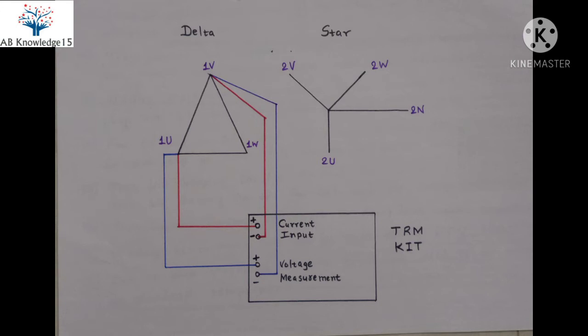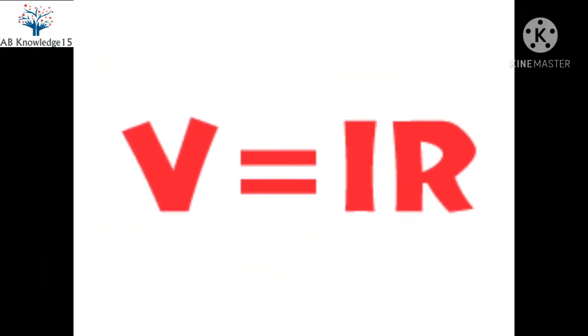For the star connection of winding, as in the case where the secondary winding is star connection, we have to connect the TRM kit phase to neutral, like 2U to 2N, 2V to 2N and 2W to 2N terminals of the transformer. After any of these connections of the test kit to the transformer, switch on the test kit, apply a suitable current range and note down the winding resistance values when we get stabilized values. In all of these measurements, the current injected by the TRM kit develops a voltage drop and resistance is measured as per the equation V equals IR.